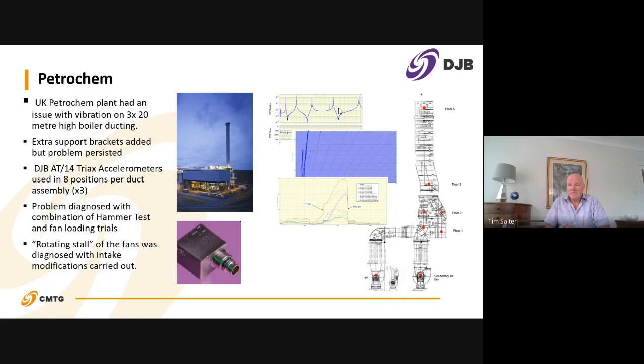And then they ran the fans with various loads and found it was a problem called rotating stall, which happens when there is insufficient airflow coming into the back of the fan to be accelerated by the fan as it comes out the other side. If you have insufficient airflow, then you have this issue called rotating stall, where the fan blades, the impellers, start to vibrate, and that was causing vibration to propagate through the structure.